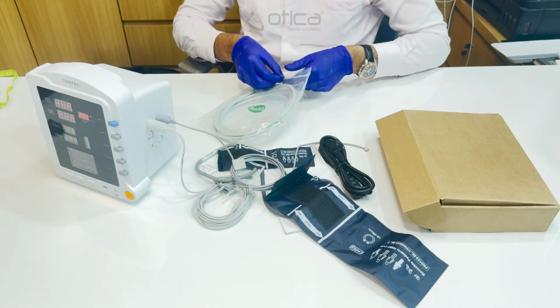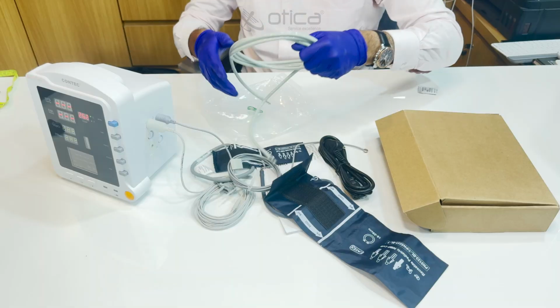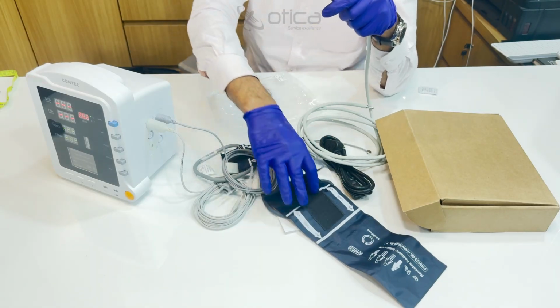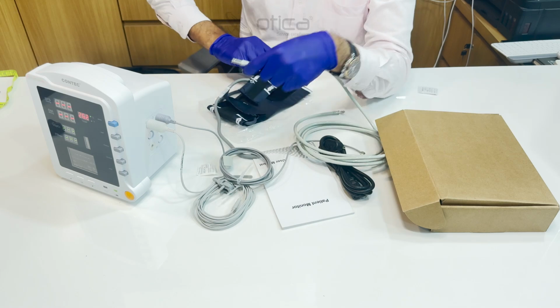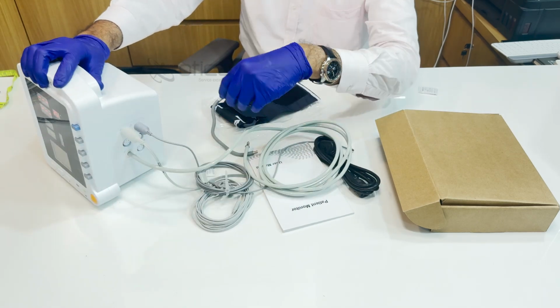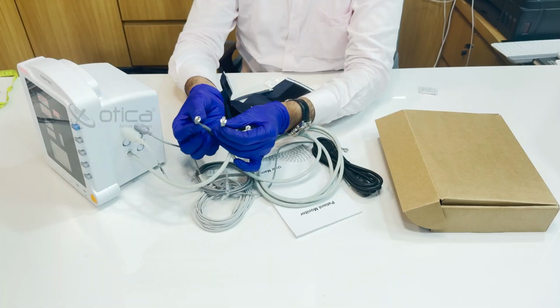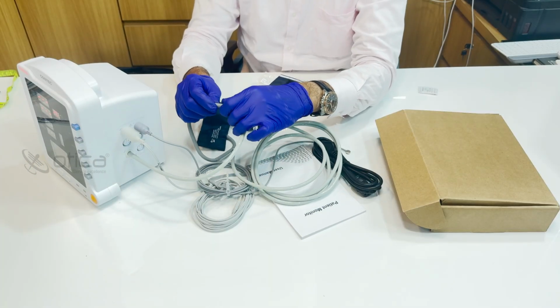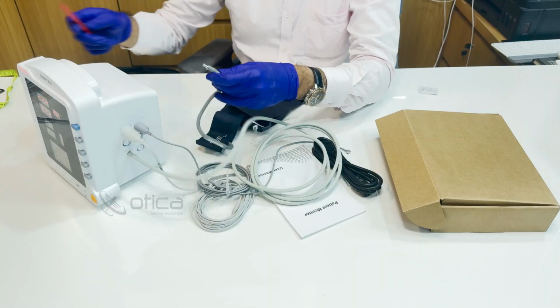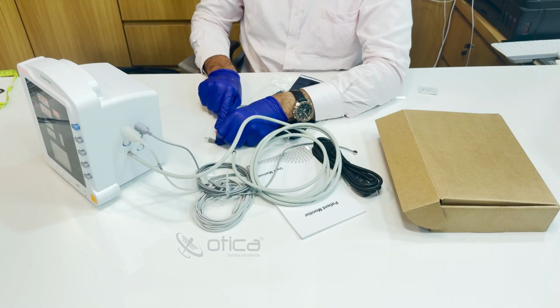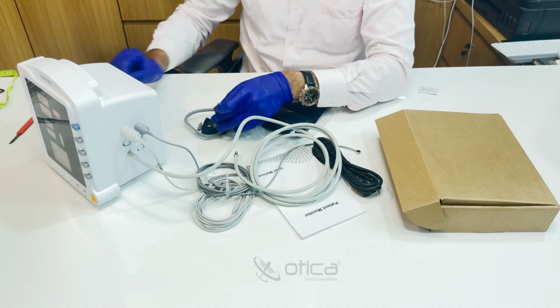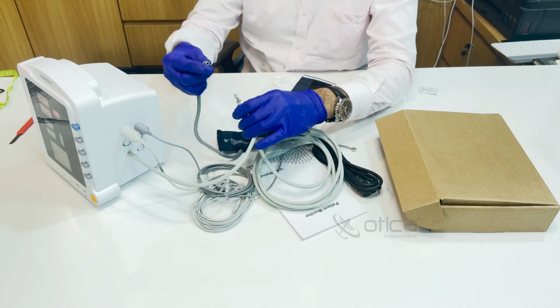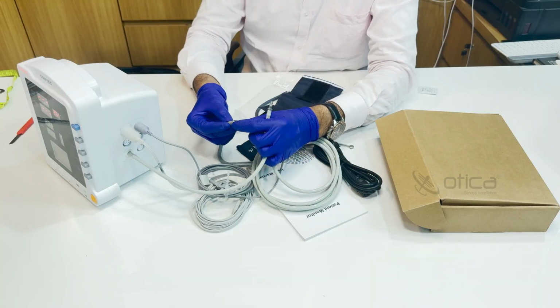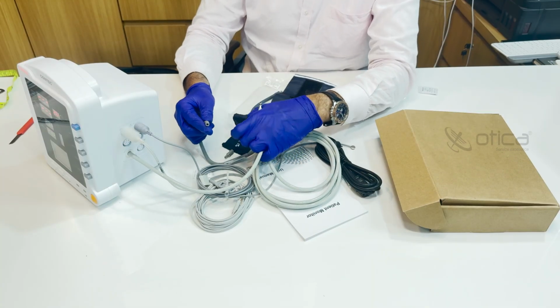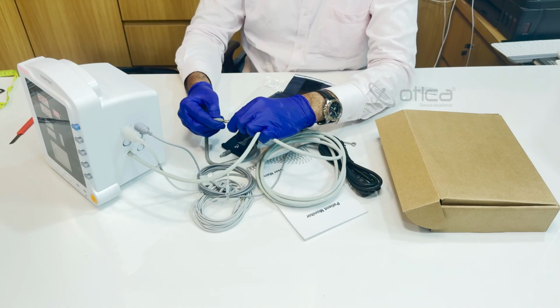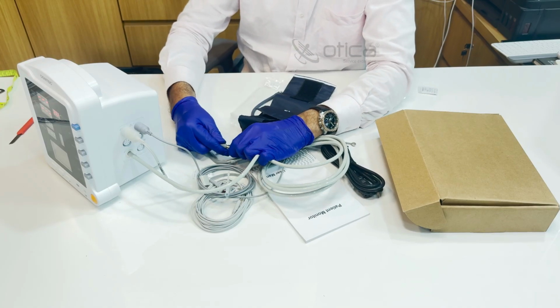Then we are going to attach the NIBP tube over here. Now you can see whenever the device is modified, there are two male to male connectors. So you just need to cut this connector from here, because this is modified for the neonatal patient. So you have to cut this connector from the cable, and you can attach this connector directly to the tube.